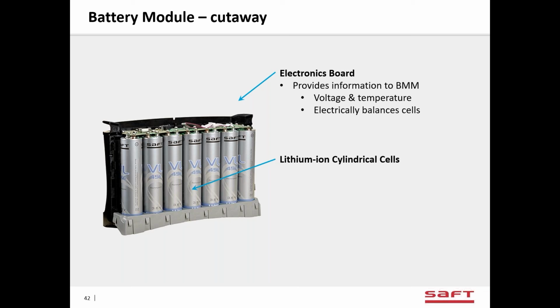There's another circuit board that goes on top of this bus bar that measures all the voltages of every cell. It measures 3 temperatures inside the module, and it also performs what we call balancing. So the cells are all balanced to the same voltage when they're on float charge, so that all the cells are uniform, and we control them to all be the same voltage. And this means if there's a little bit of difference in capacities or self-discharge, all the cells are at the same voltage ready for a discharge.